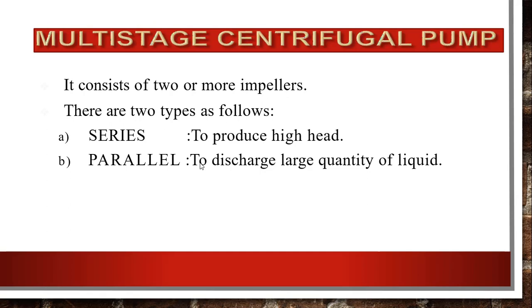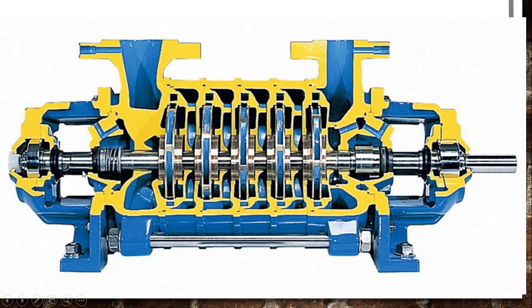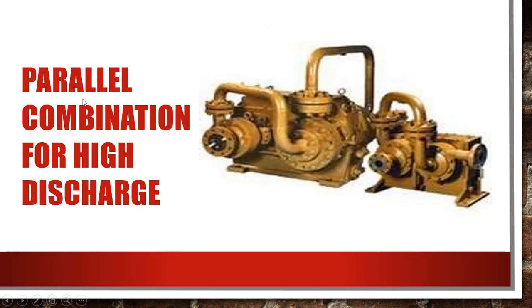A multi-stage centrifugal pump consists of two or more impellers. There are two types: series connection, which is used to produce high head, and parallel connection, which is used to discharge a large quantity of liquid. In series configuration, the impellers are placed in series along the shaft for creating high head. In parallel configuration, the impellers generate high discharge.